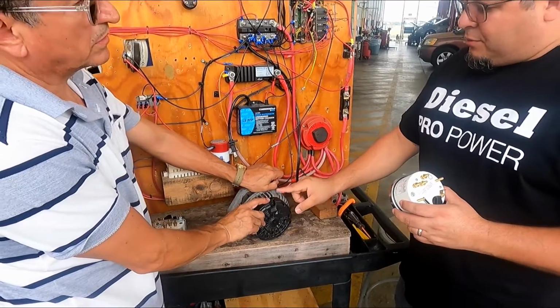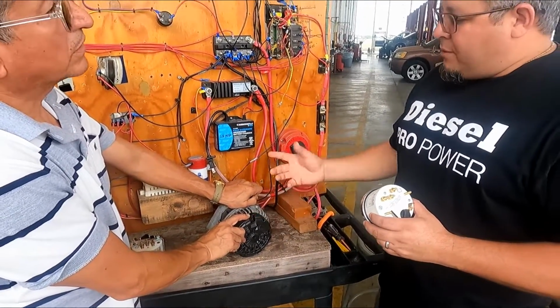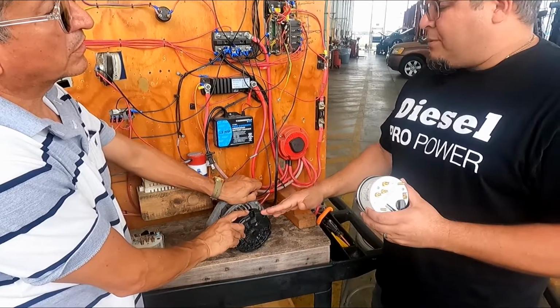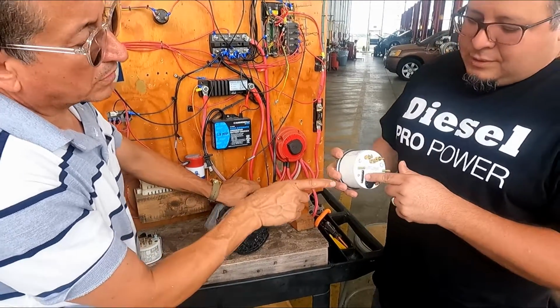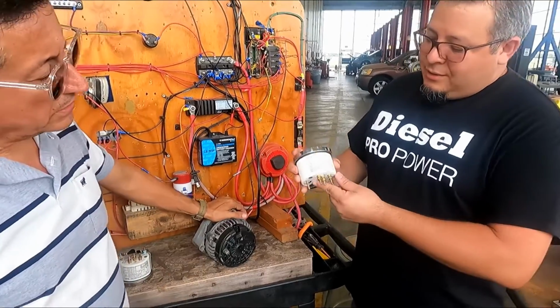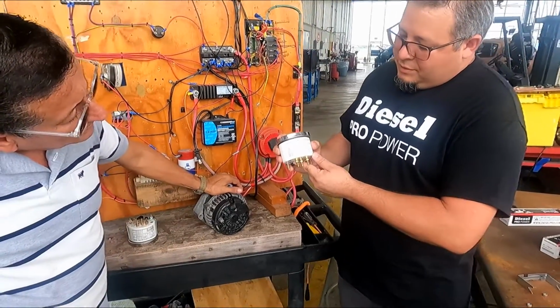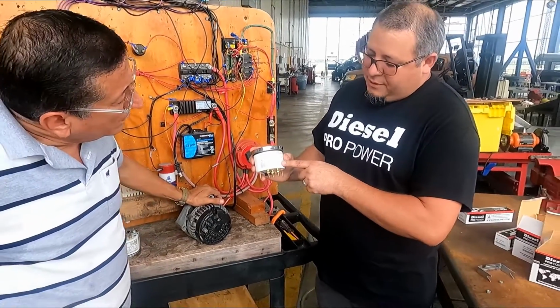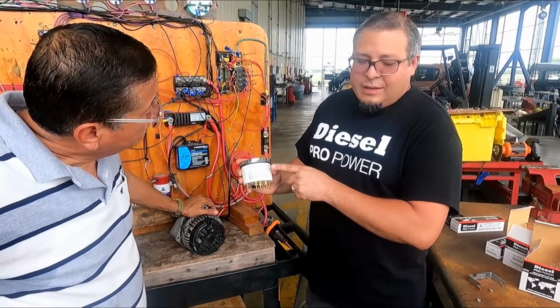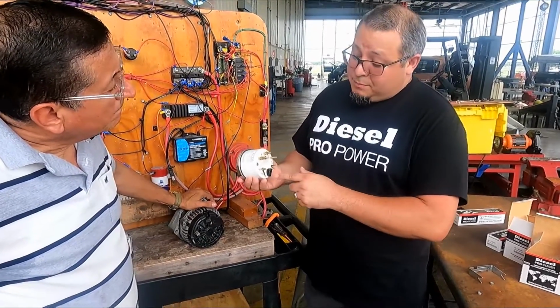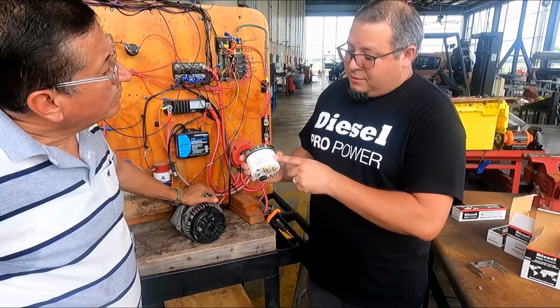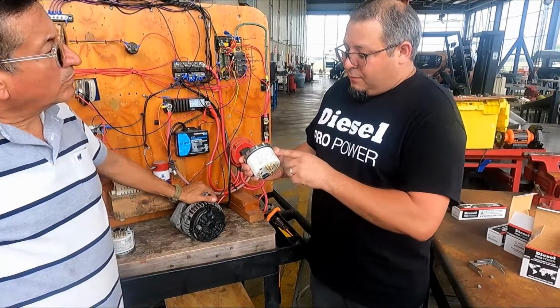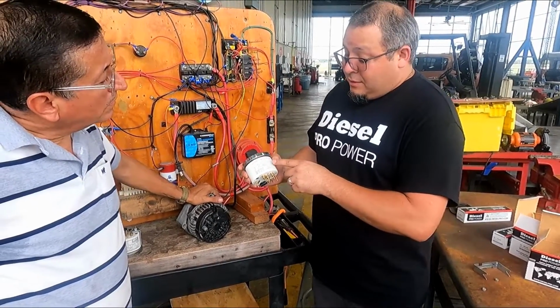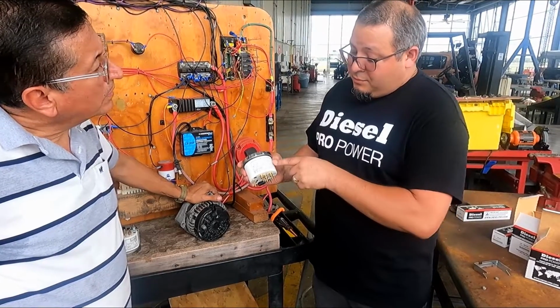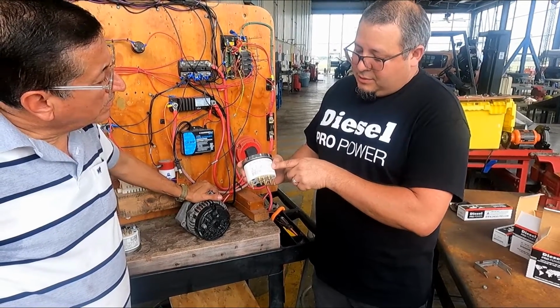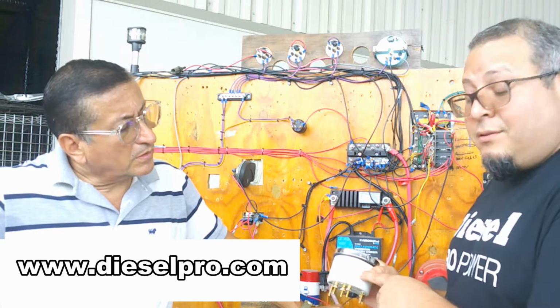It sends the pulses to the tachometer, which reads the pulses. You calibrate it with the dip switches in the back. Each tachometer brings the calibration signals, so you can position the dip switches in the correct positions. For example, if it's reading 3 or 4 pulses that determines 1 RPM, you calibrate the dip switches exactly as mentioned in the tachometer's instructions.